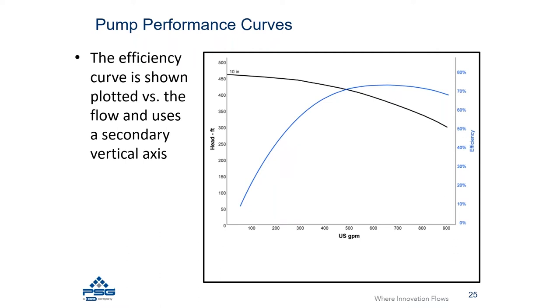For all centrifugal pumps, at very low flow rates the pump is very inefficient. As you move to the right of the curve, efficiency increases quite quickly until it hits a peak. That peak is called the best efficiency point, or BEP, which is the ideal operating condition for a centrifugal pump to achieve the most efficiency and best reliability.